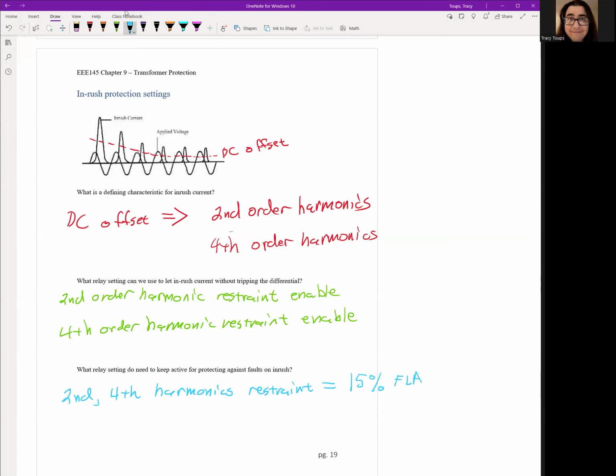restraint setting. Now, one thing to note is during inrush, we're literally disabling our main protection scheme, the 87 differential. So what happens in the very, very, very rare chance there's a fault in the transformer from the manufacturer, and when we try to energize, there's a fault. We disable the 87 element, so that's not going to help us. So no matter what you do, always at least have something to save you at all times. So even if we disable all the protective settings in the relay, keep at least one. And we always say keep a 50 element active. Okay. Just in case in that one-off chance there's a fault when we try to disable everything else. So keep a 50 element active as backup.